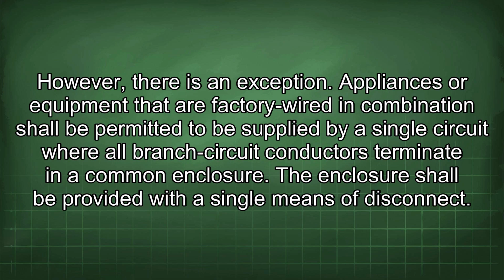However, there is an exception. Appliances or equipment that are factory wired in combination shall be permitted to be supplied by a single circuit, where all branch circuit conductors terminate in a common enclosure. The enclosure shall be provided with a single means of disconnect.